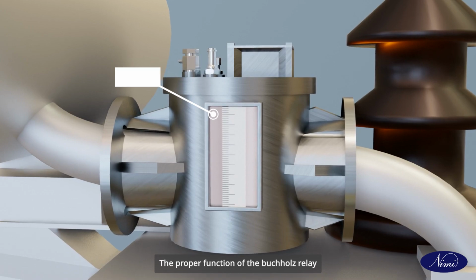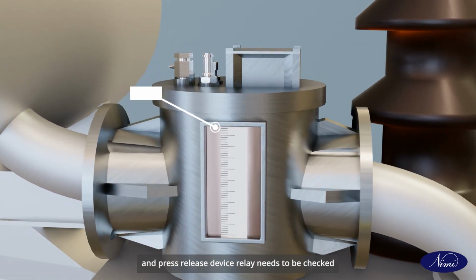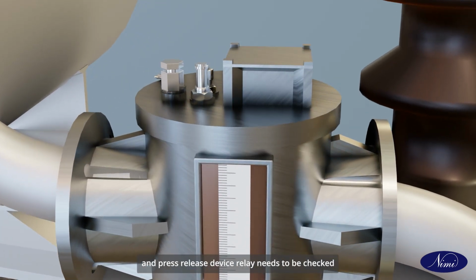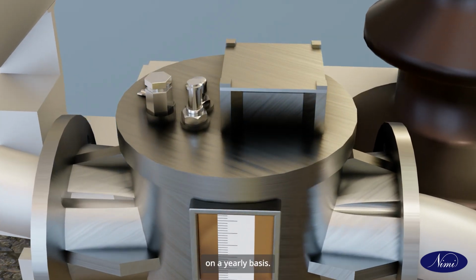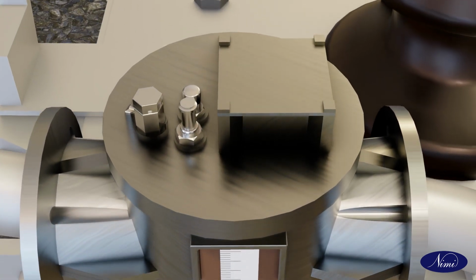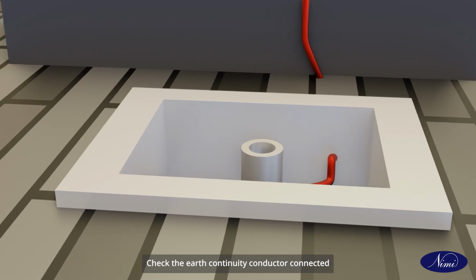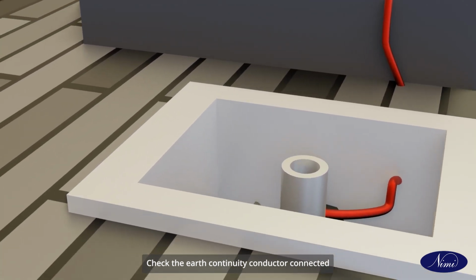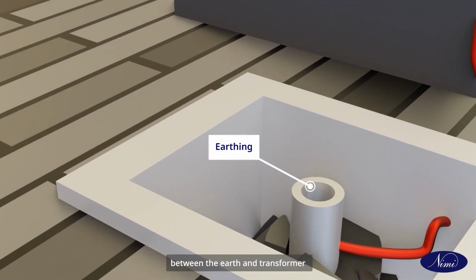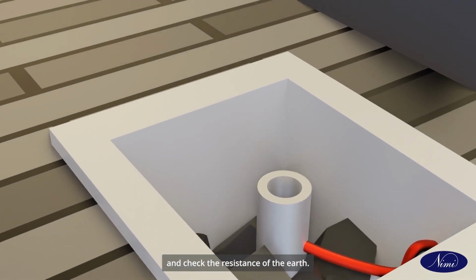The proper function of Buchholz relay and pressure release device relay needs to be checked on a yearly basis. Check the earth continuity conductor connected between the earth and transformer and check the resistance of the earth.